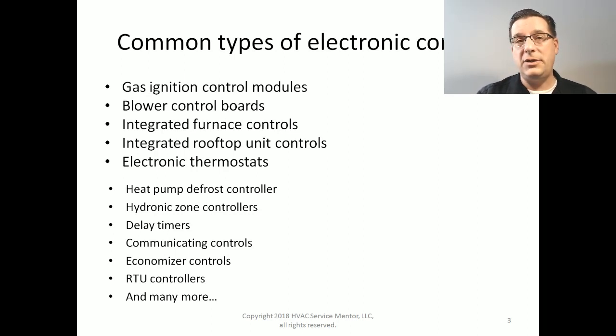And under part load conditions, the energy efficiency of the air conditioning machine is less than what it is at full load. Because our equipment operates at part load almost all the time, and it operates at full load very infrequently, it makes a lot of sense for us to vary the capacity of our air conditioner to match the demand. And in so doing, maintain the energy efficiency of the unit. And that level of control requires some very sophisticated operations controlled by electronic control boards. In one of our slides down the road, we're going to see a unit that does exactly that. Another great example of that is inverter drive mini split air conditioners. They do that, and they have a ton of electronics in them to make that happen.